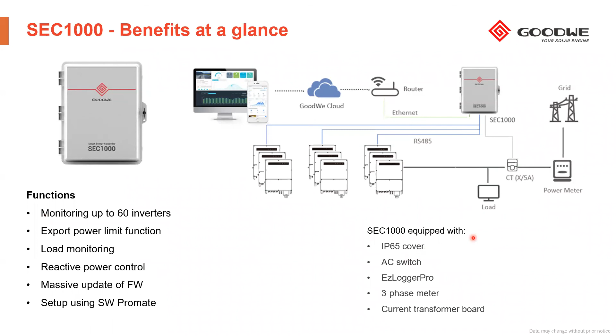So we have seen the real SEC 1000. This is the part that we have seen already, so no need to stop here. But this is important to highlight here. Probably the most important thing, when we apply the SEC 1000, we need to pay attention carefully to the selection of the current transformer. The current transformer is X/5. That means the X is the primary. First of all, we need to select the type of current transformer based on the electrical installation in the facility. If it's a bus bar or wiring, right? It's not the same. Here could be applied for both, right?